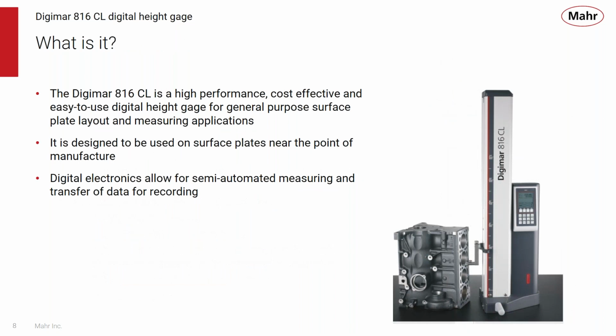So what is it? The 816 CL is a high-performance, cost-effective, and easy-to-use digital height gauge for general-purpose surface plate layout and measurement applications. It's designed to be used on a surface plate near the point of manufacture. So it doesn't have to be relegated to the quality control room or the incoming inspection area. It can be used right near the point of manufacture. And with its digital electronics, it allows for semi-automated measuring and transferring of the data for recording. So it's a pretty full-featured height gauge.